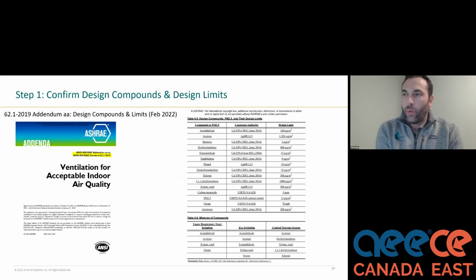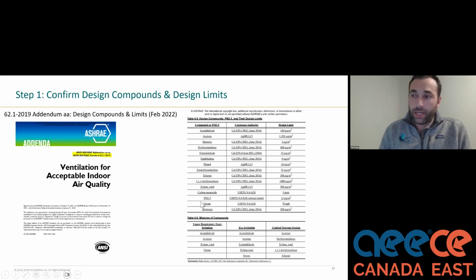So just showing you here what the design compounds and limits are within ASHRAE 62.1 2019. The big one on this list is really things like formaldehyde. Formaldehyde has a very low design limit and a very high emission rate, so that's typically what drives the calculations. So if you see an IAQp calculator out there that's blowing up this design limit, it's probably not going to pass muster. Another interesting contaminant on here that I'll mention is ozone. Ozone's an outdoor generated contaminant, so it's not one of those contaminants that we can actually ventilate out of buildings. It's coming from the outside.